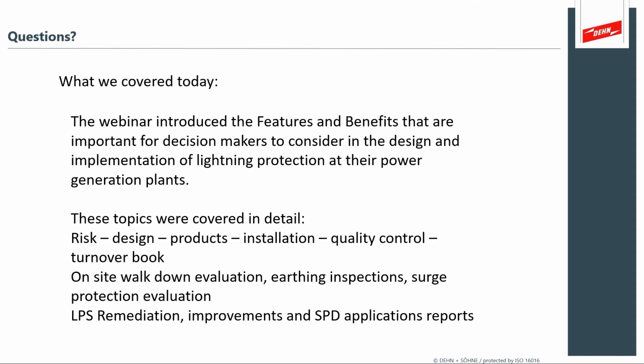And we know from simulations that, on these power fields, they most likely will be less than 10 ohms if we do a fall-of-potential method here. But they comply with the dimensions and the shape requirements, and thereby we will know that the dispersion of lightning current will be really good into the soil, and we have touch and step potentials that are acceptable. So yes, I agree with you, Mark.